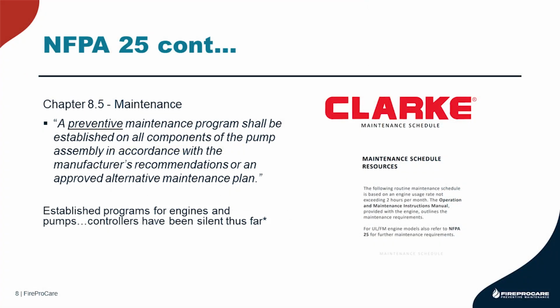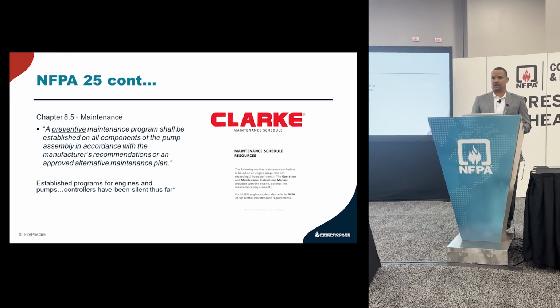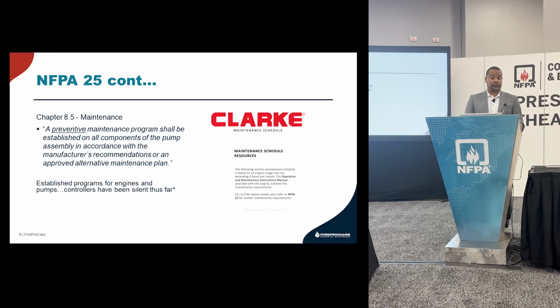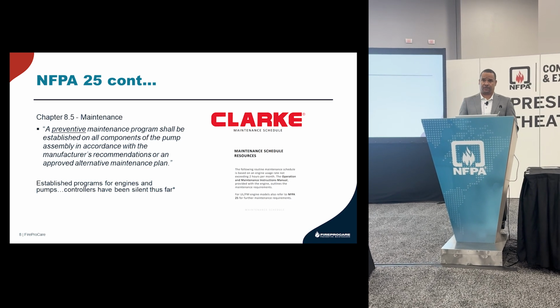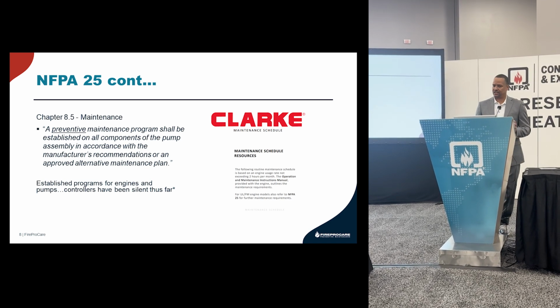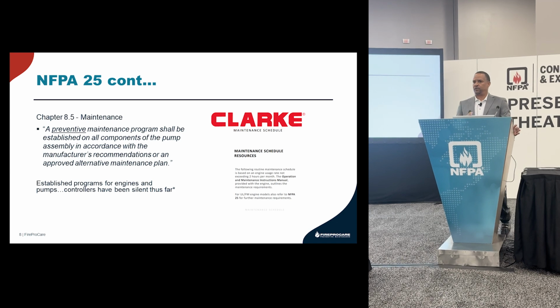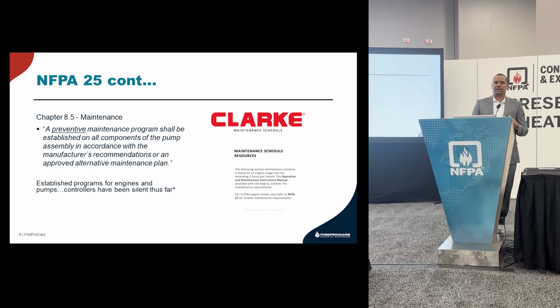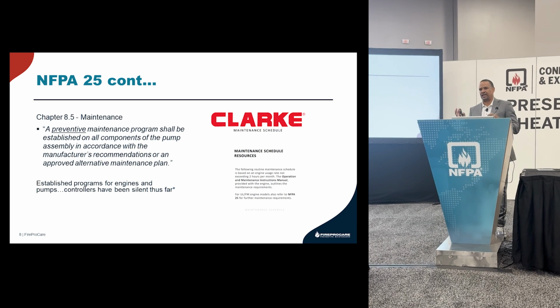Chapter 8.5, which is the reference chart 8.1.2 points you to, is straightforward. My goal is to answer why you need preventive maintenance. It's in black and white in NFPA 25: a preventive maintenance program shall be established. It doesn't say should be or could be—it says shall be established. Yet no one has done it. No one has established a program for the fire pump controller. That's the most important message I need you to take from this.